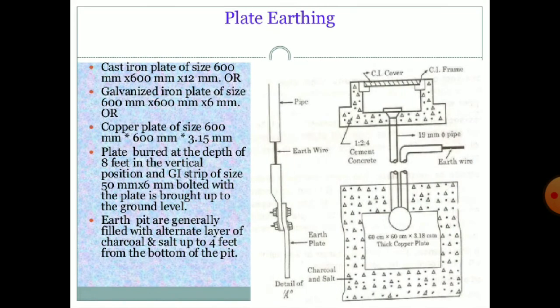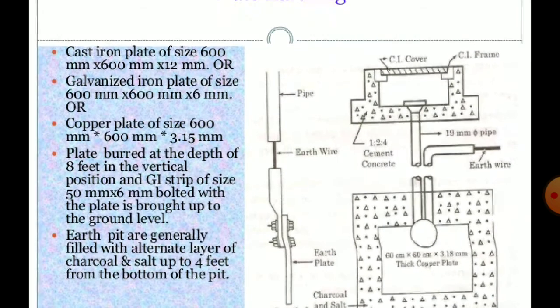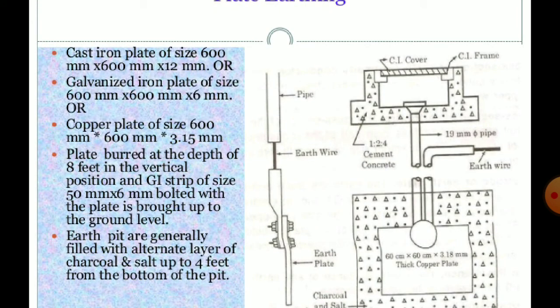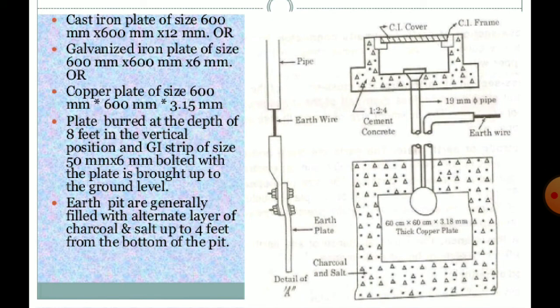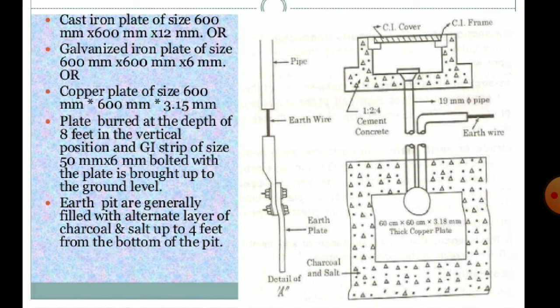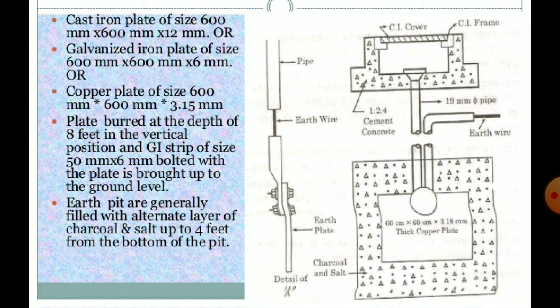Another type of earthing is plate earthing. Here the plate is made of copper, or we can take a galvanized iron plate. If you take a galvanized iron plate, the size is 600 mm by 600 mm with 6 mm thickness. If you take a copper plate, the size should be 600 mm by 600 mm with a thickness of 3.15 mm. This will be buried under the earth at a depth of 8 feet and has to be placed vertically. After placing this plate, we bolt one GI strip to it for taking external connections to the ground level. Here also the plate is surrounded by layers of charcoal and salt so as to maintain the moisture level.